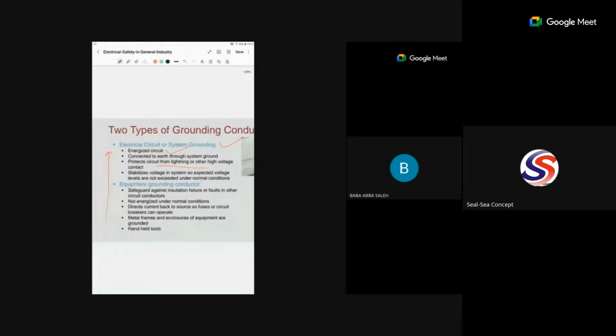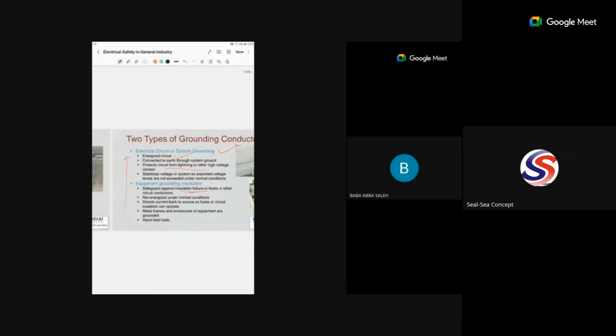You can also do earthing of equipment, meaning the body you think is not a conducting part, if anything goes wrong with the installation, there may be conduction. So to avoid that risk, even parts of the machine not meant to conduct electricity need to be grounded and connected to the earth.